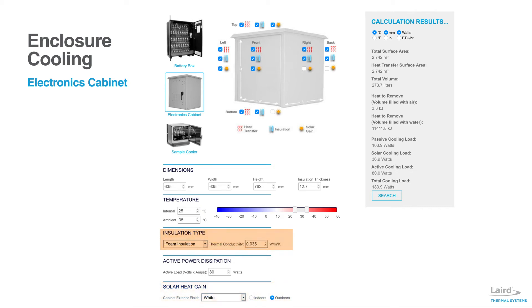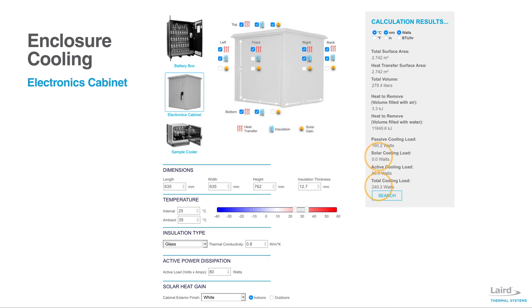In this case, we are going to add a glass door at the front. Therefore, we will take the insulation away from the glass door and eliminate the solar gain since this is an indoor application. Notice that as we make those changes, the cooling load is constantly being updated on the right side under calculation results. Our total requirement is 240.2 watts, of which 80 watts come from our active dissipation, while the other 160.2 watts is passive.